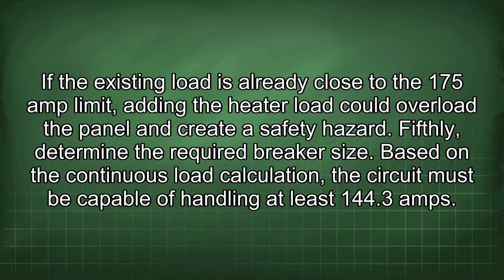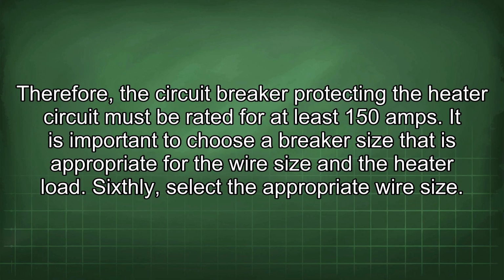Fifthly, determine the required breaker size. Based on the continuous load calculation, the circuit must be capable of handling at least 144.3 amps. Therefore, the circuit breaker protecting the heater circuit must be rated for at least 150 amps. It is important to choose a breaker size that is appropriate for the wire size and the heater load.